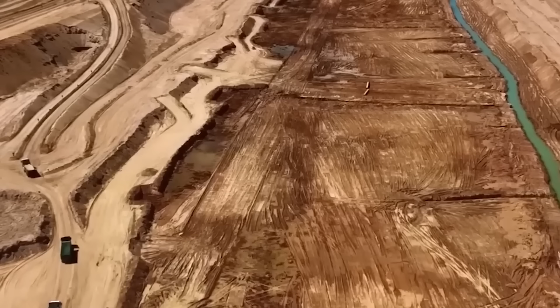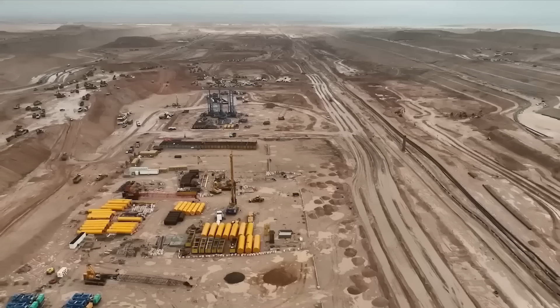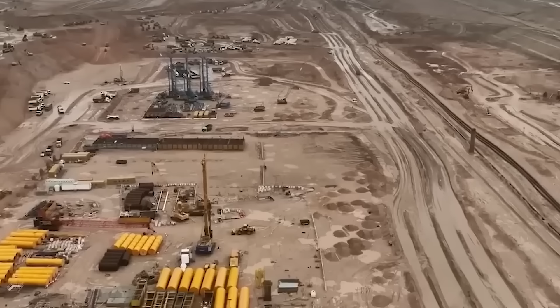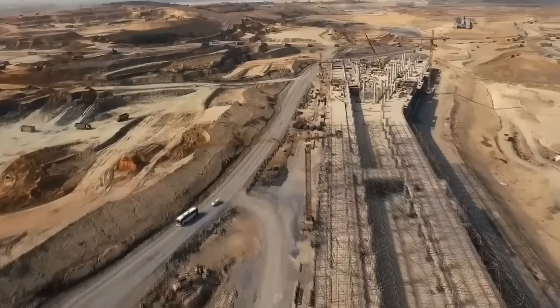The problem for any claim of completion is that even if one module is far ahead structurally, you still need it to be habitable, and habitability is dominated by the slowest, most integrated tasks: fire compartmentation, life safety systems, elevators and vertical transport, power distribution and backup, HVAC balancing, water systems, pressure testing, control system tuning, and the testing regime that proves the whole environment behaves under load.